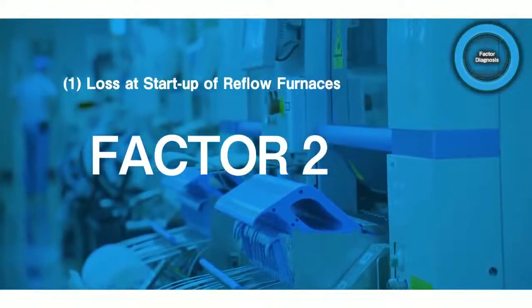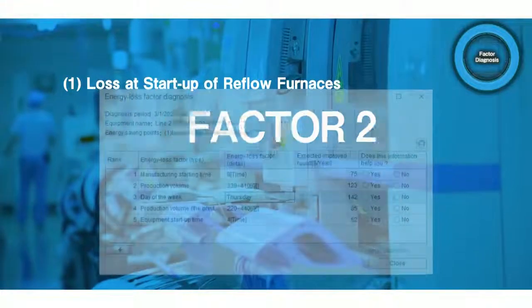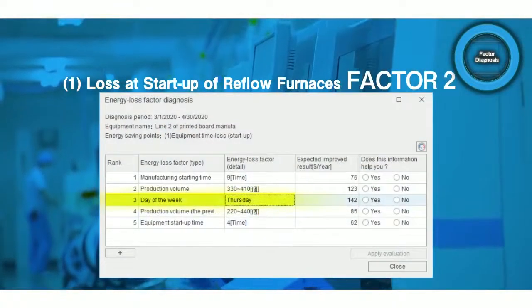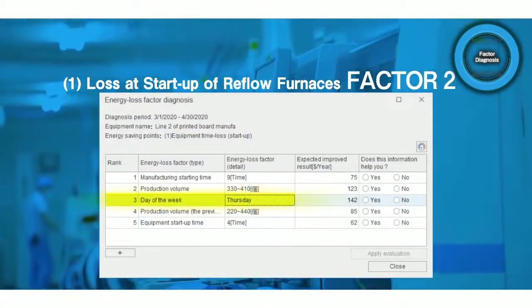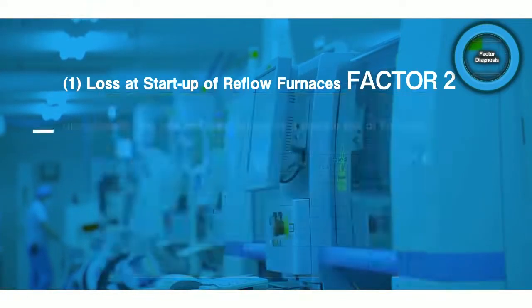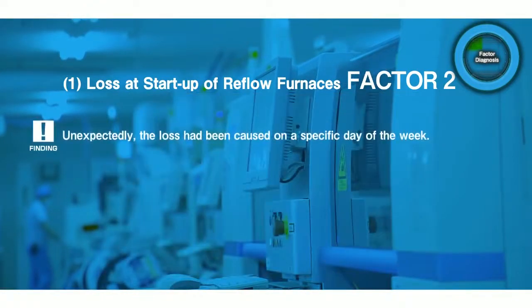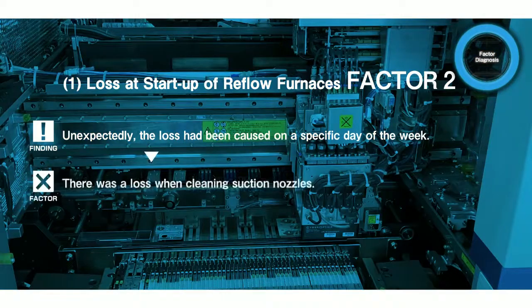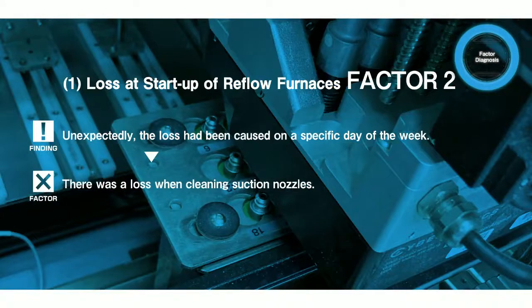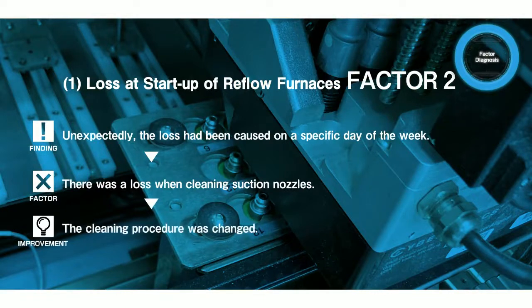Another factor of loss that the diagnostic results showed was, unexpectedly, a specific day of the week — Thursday. This was an unexpected factor that could not be detected by humans and was one that could only be diagnosed by AI. By checking the on-site operation, loss was found in the cleaning of suction nozzles, which is done only on Thursdays. Based on this finding, the cleaning operation was improved.